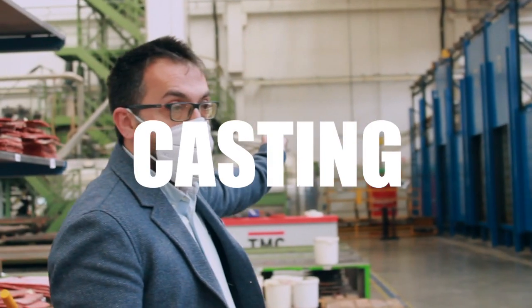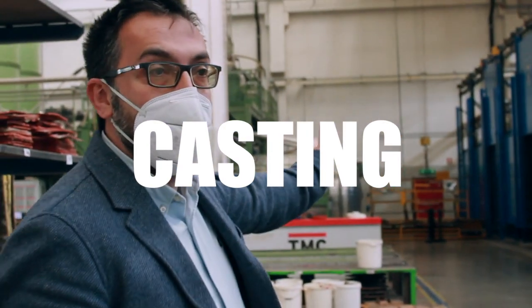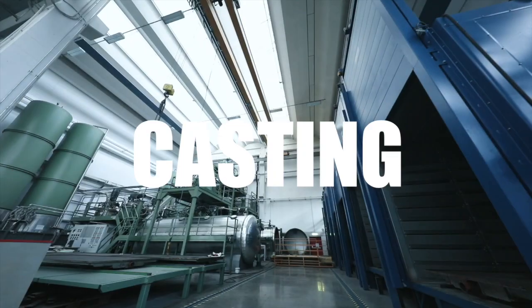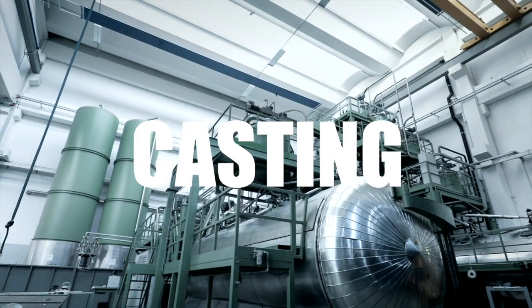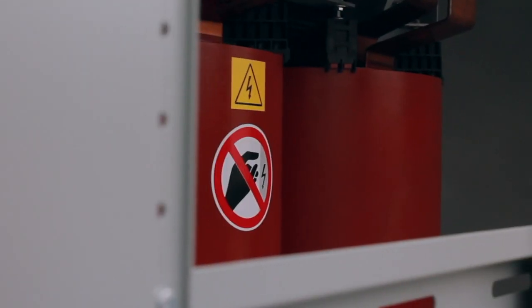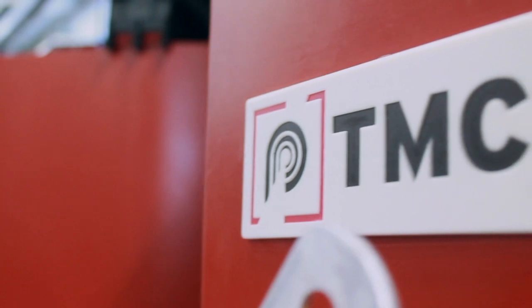In this casting department, we are able to cast medium voltage and low voltage coils. We have two independent facilities using different resins: one in class H, for insulation materials up to 180 degrees maximum working temperature, and one in class F, up to 155 degrees. The choice of resin depends on customer specification and the application of the transformer.